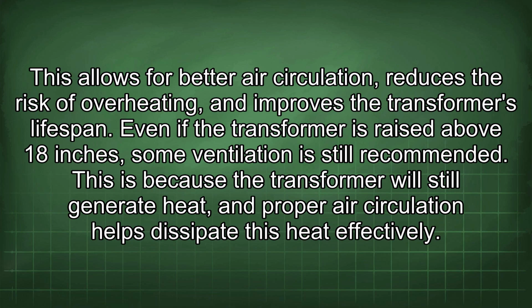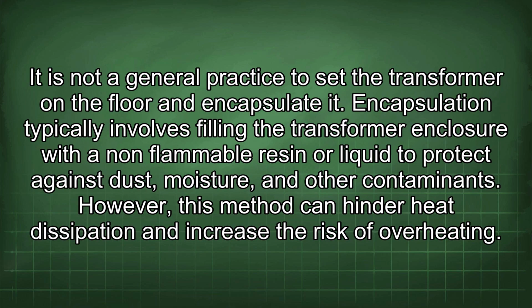Even if the transformer is raised above 18 inches, some ventilation is still recommended. This is because the transformer will still generate heat, and proper air circulation helps dissipate this heat effectively. It is not a general practice to set the transformer on the floor and encapsulate it. Encapsulation typically involves filling the transformer enclosure with a non-flammable resin or liquid to protect against dust, moisture, and other contaminants. However, this method can hinder heat dissipation and increase the risk of overheating.